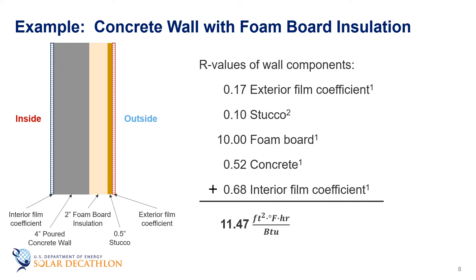Now, there are a couple of interesting observations here. One is that the resistance of the concrete is very, very small — and even though it's pretty thick, that concrete is highly conductive. The second observation is that the film coefficients together have a higher resistance than the concrete. So the foam insulation is dominating the insulation value of this wall. We can use this technique of adding up R-values for any wall made up of consistent layers where the foam is continuous across the entire wall and the concrete and stucco are continuous and homogeneous.